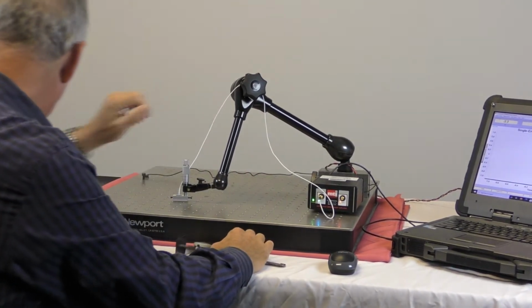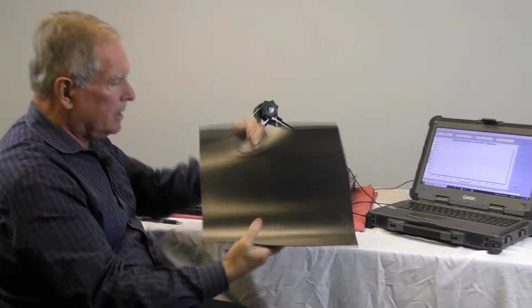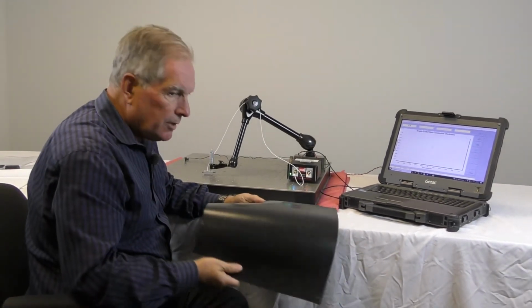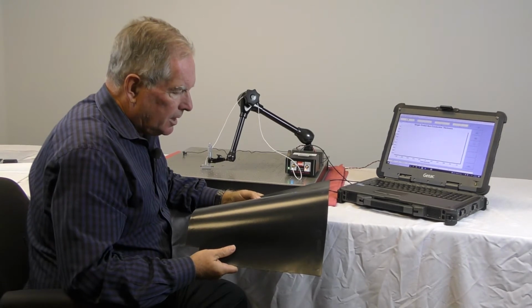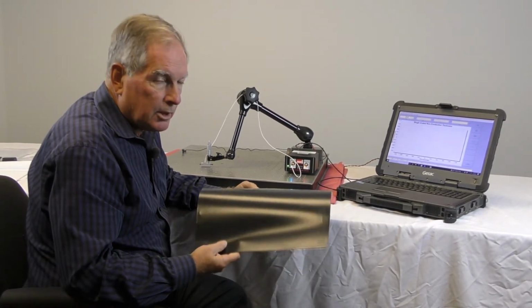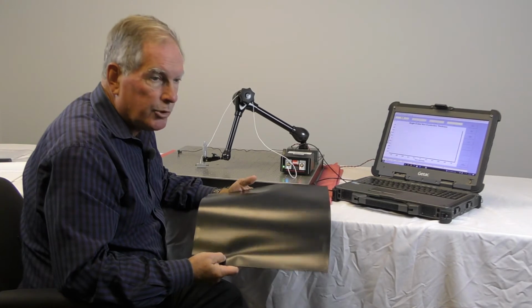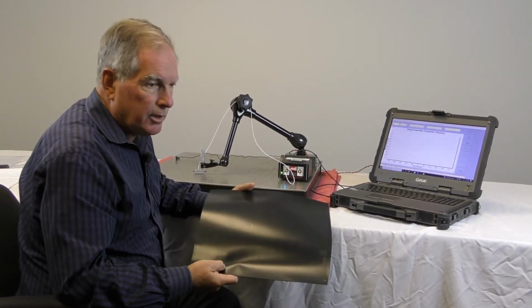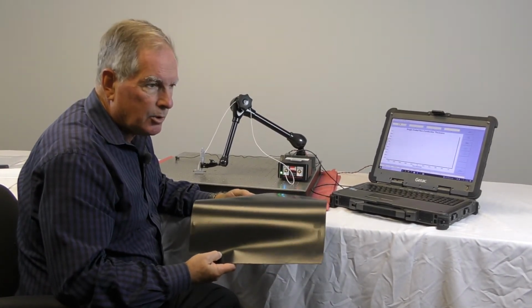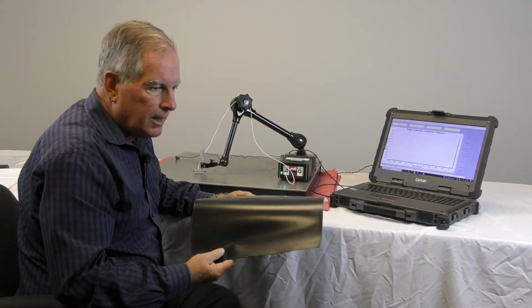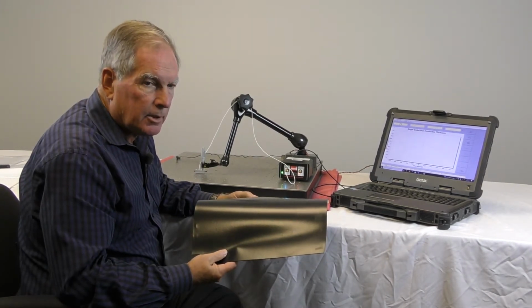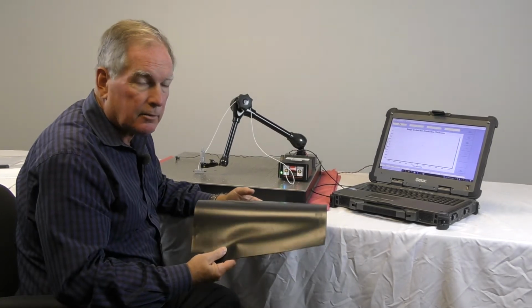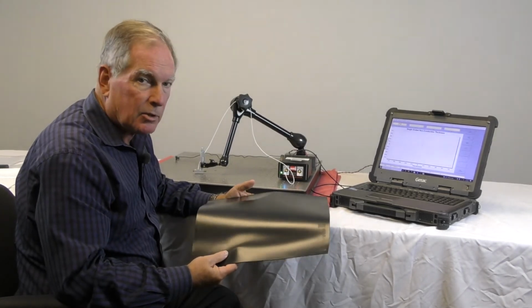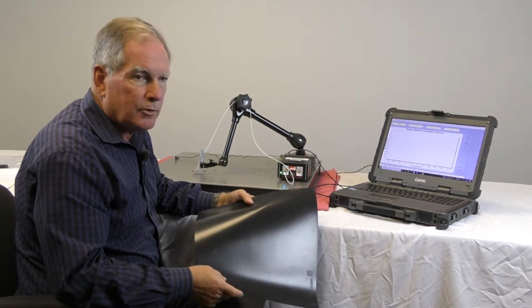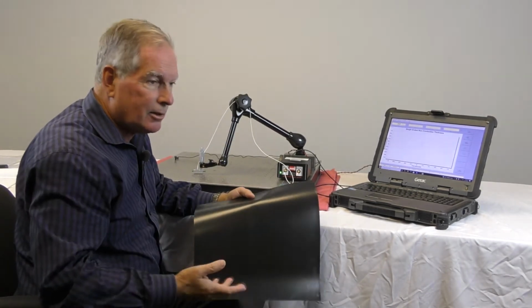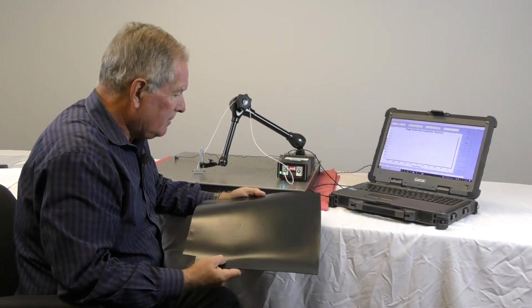But before we do that, I wanted to talk a little bit about the non-conductive materials, and this is one of them right here. There are some do's and don'ts with these. Number one, they can't have holes in them. They can't be wet. So you can't have this in a process where it's soaking wet or soaked with any kind of highly conductive material. And water is actually, believe it or not, highly conductive. It has a dielectric constant of 80, which makes it almost like a conductor. We all know that if you're standing in water and you touch an electrical socket, you're going to get killed, and that's because it's mostly conductive.